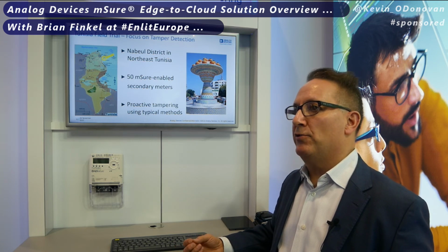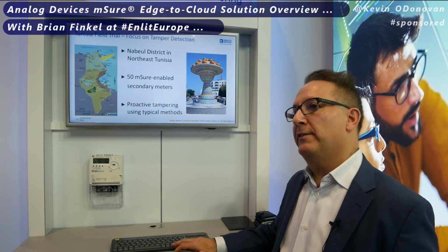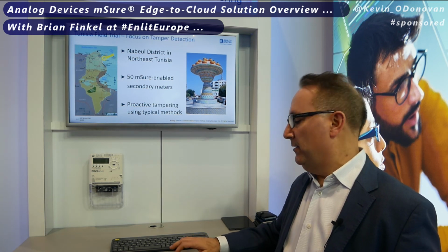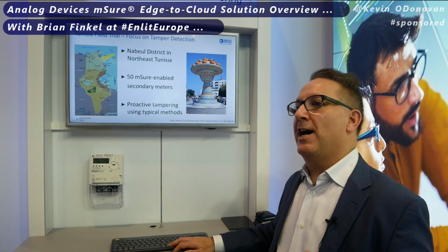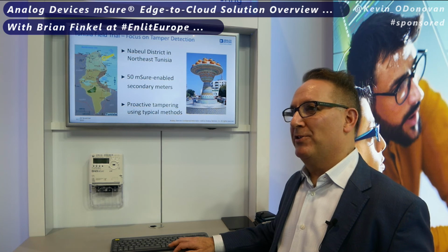Next, we talk about the field trial in Tunisia. And this was all about energy theft detection, right? We installed 50 of these meters in the field in a high theft district. And we used proactive methods to detect tampering. So what that means is, instead of waiting for, say, end customers to tamper with these meters, we had an expert field worker go out and do the tampering the way tampering is done in Tunisia. And out of the 50 meters, 37 tampers were applied. And of the 37, the mSure solution detected 36 of the 37 detectable tampers. So it was quite a positive result.